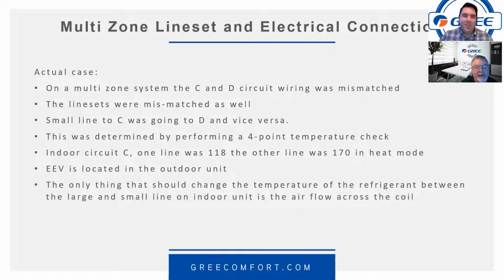So a remedy for that, and I could see if somebody's hooking up a multi-zone system, they're going to shove a lot of pipes through the wall at once, right? But they should tape the sets together. You know, this is set A, set B, set C, whichever set of valves you're going to go to on the system, and then same with wiring, right? Yeah, different colored electrical tape seems to be a good idea. That way you know this one's with this one. Right. Yeah, because that could certainly be problematic.